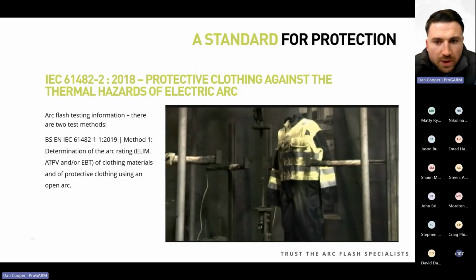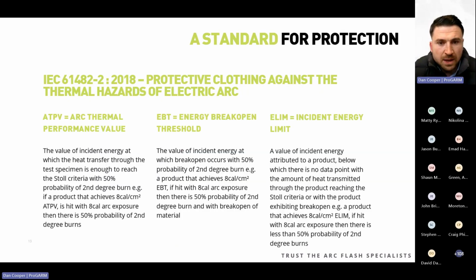I'll show you the other one shortly, but it's important to note that these two tests are independent of each other. The tests also provide ratings. There are three acronyms on the screen: ATPV, which is the arc thermal performance value, the EBT, which is the energy break open threshold, and the ELIM, which is the incident energy limit.